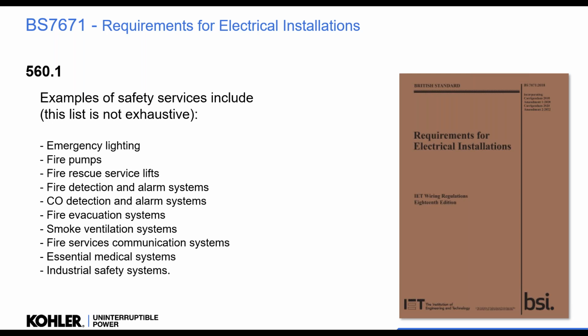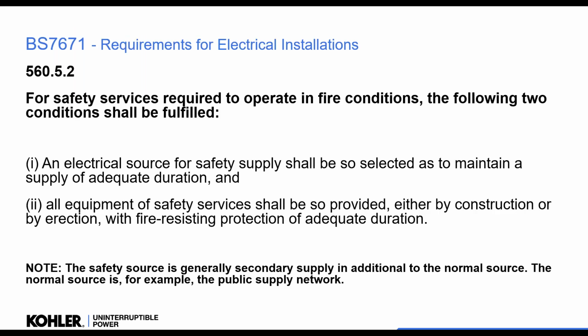It gives us an example of them: emergency lighting, pumps, fire lifts, evacuation lifts, medical systems, smoke extract, all these things. It says it's not exhaustive, it's any system that protects life and property. Okay, so that's a safety system. So it can be a very wide range of equipment that needs to be supported now. So it says for safety services, it's required to operate in fire conditions. You have an electrical source for safety supply that is to be maintained for the supply of adequate duration.